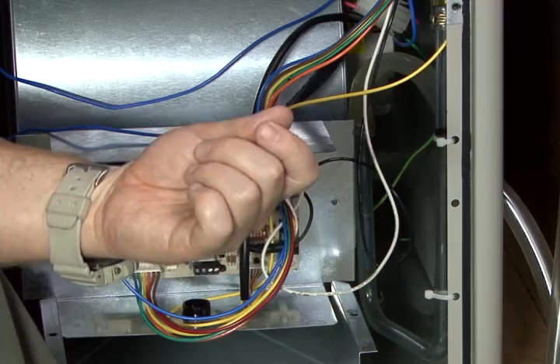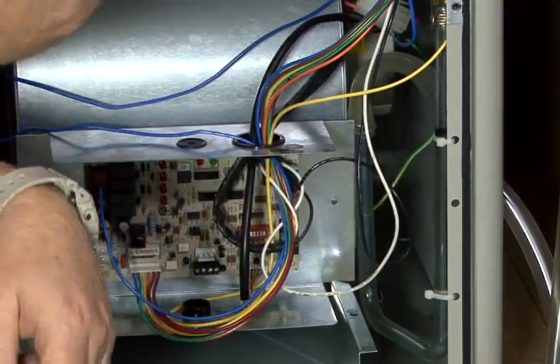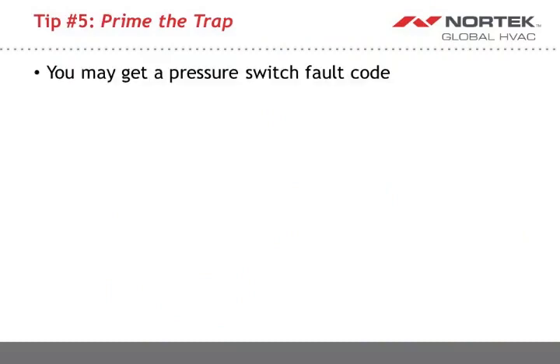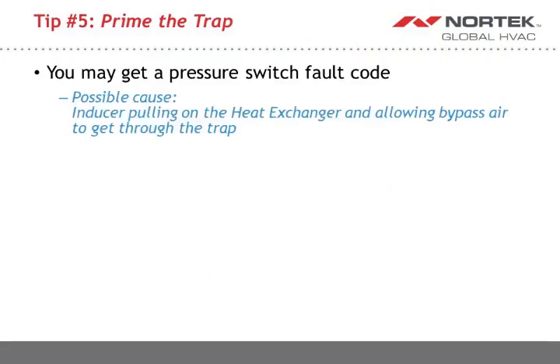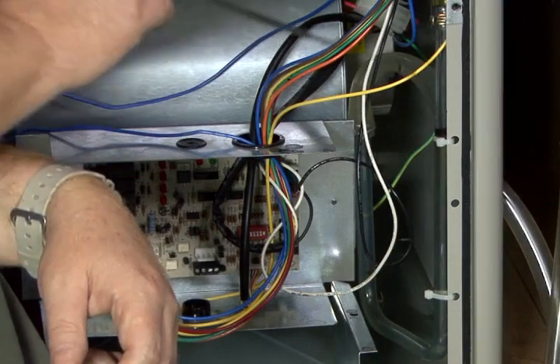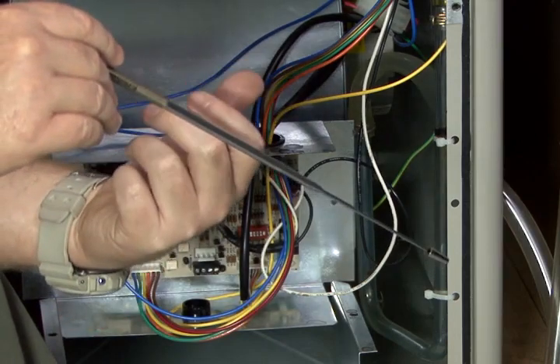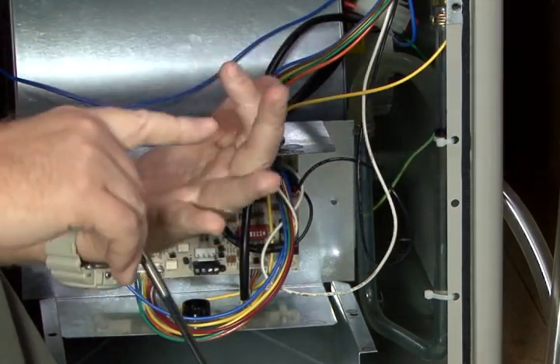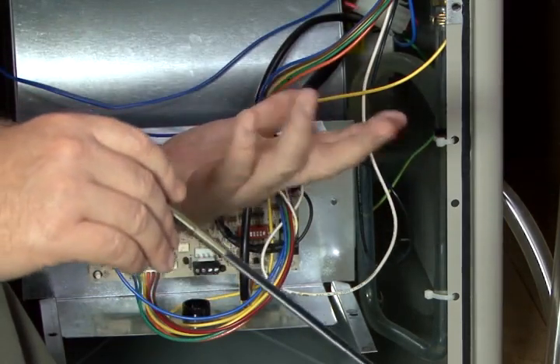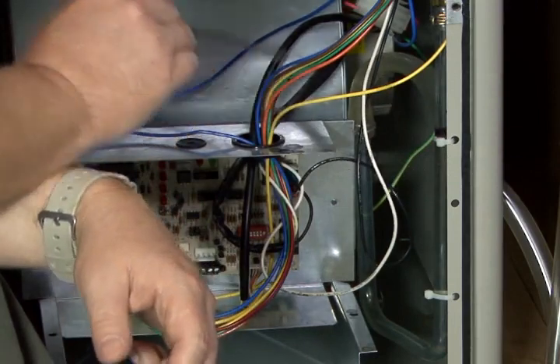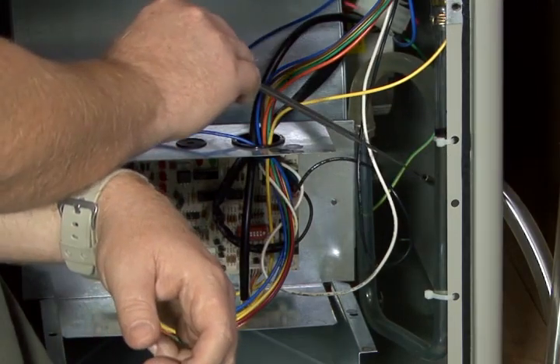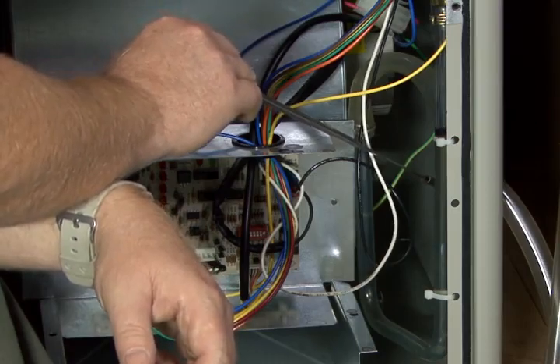If by chance you don't get that trap primed with water, what can happen is that when you first start that furnace up to do your checkout procedure, you may discover that you're getting a pressure switch fault code. That can result from the inducer pulling on the heat exchanger and actually allowing bypass air to get through that trap because it doesn't have any water in it. So make sure that every single time that you do an installation on a high efficiency gas furnace, whether it be 92%, 95%, even on a modulating 97% gas furnace, make sure that before you do your startup and checkout procedure that you prime that plastic J-tube trap with water.